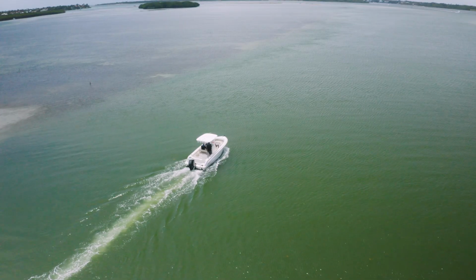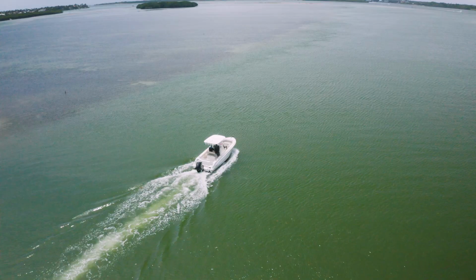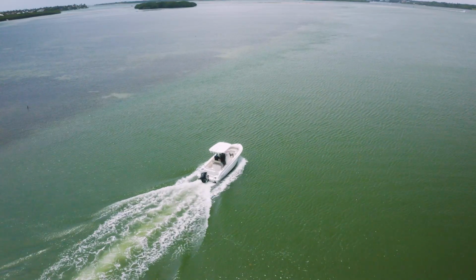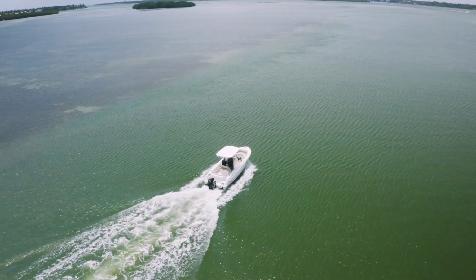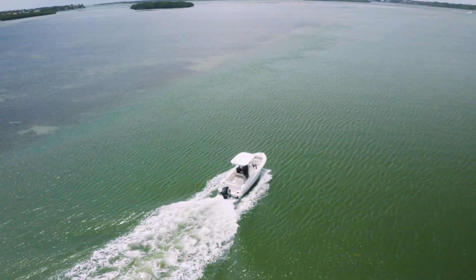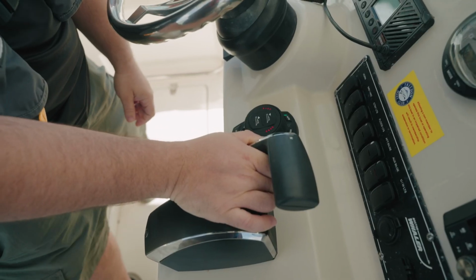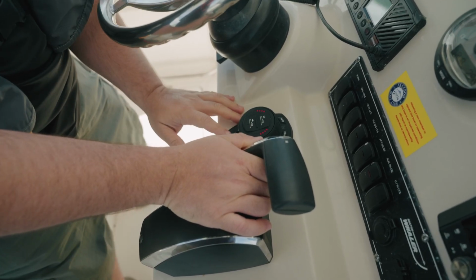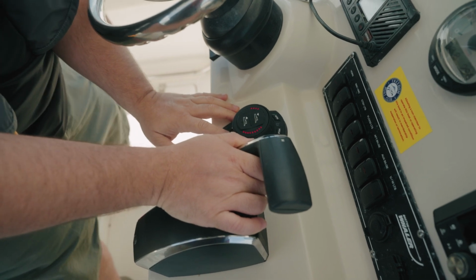We're going to watch for those lights to flash. And then when those lights do flash, we're going to do a press and hold of the dim button on the keypad to store that position. It's very important when doing this that we don't overshoot. We don't want to over throttle too fast and run into a situation where we store a point that is beyond that triggered flash. So again, you want to watch for that flash, hold that position, store it, and then we're ready to move on to the next step.